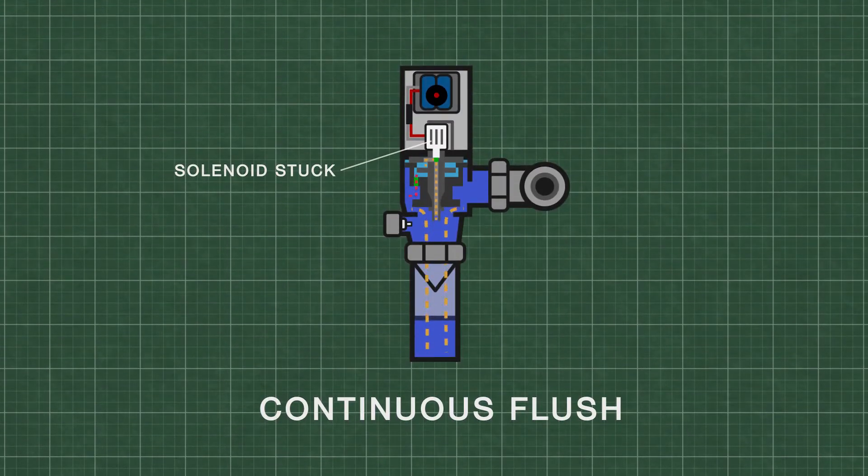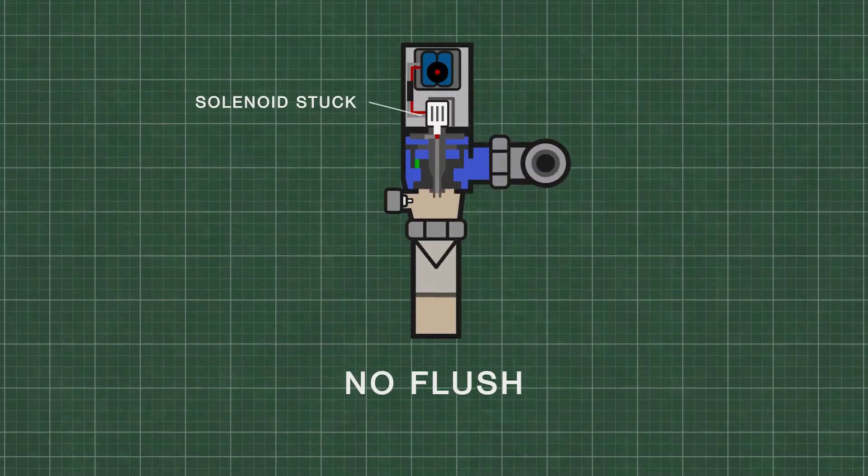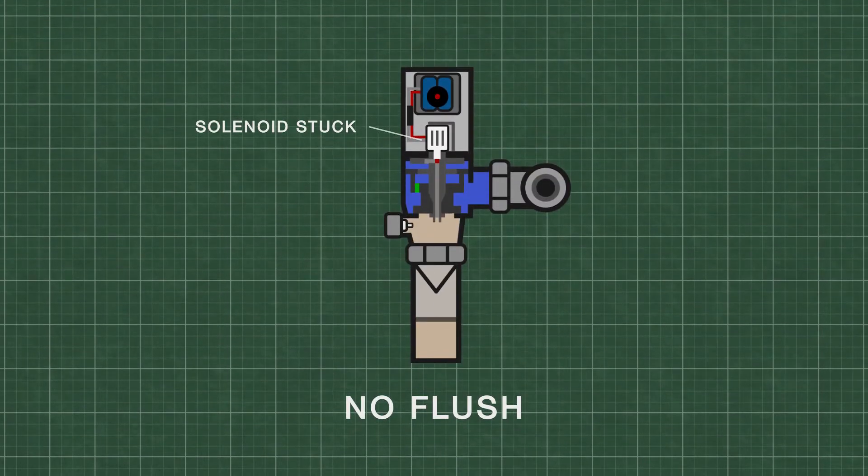If the solenoid is stuck open, it can cause continuous flushing as water continues to flow out and prevents the upper chamber from filling with water. If the solenoid fails to open, it can prevent the unit from functioning at all.